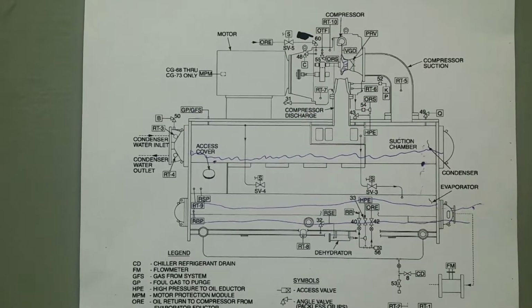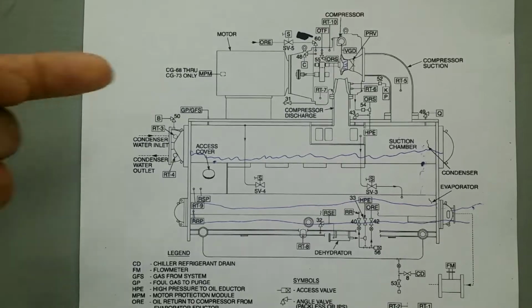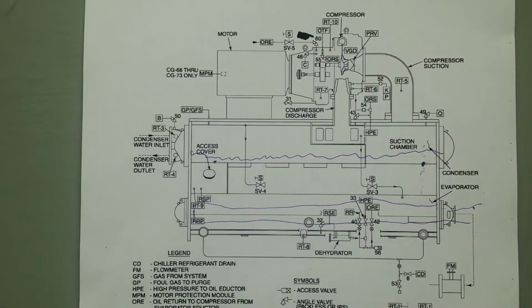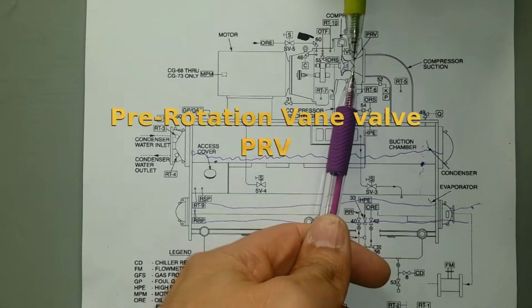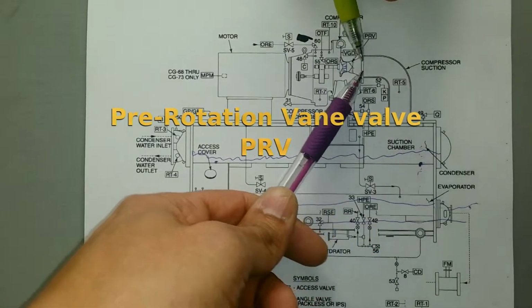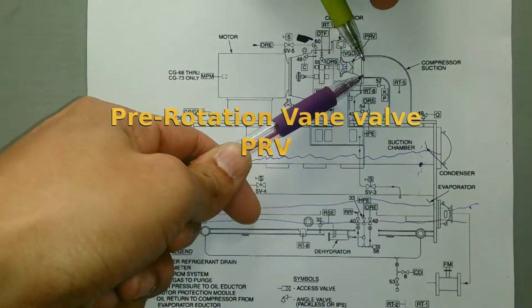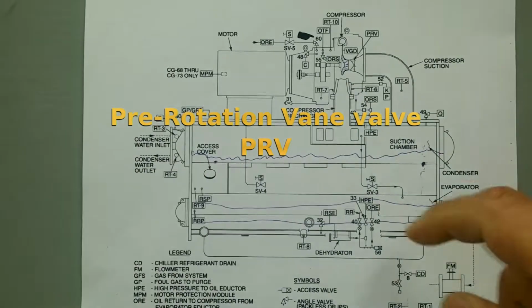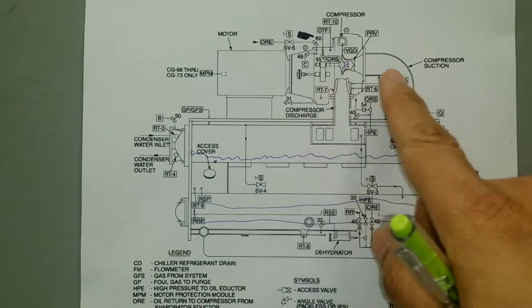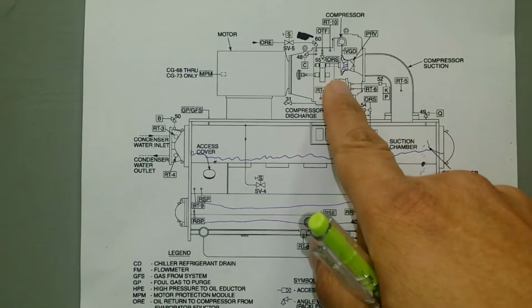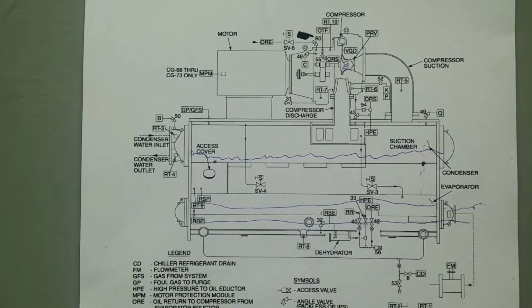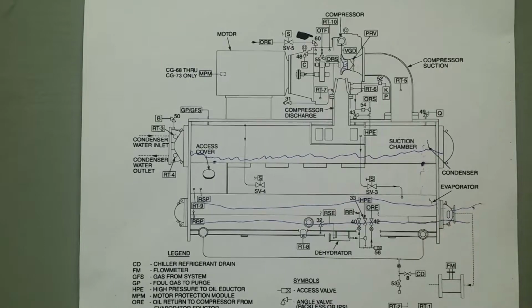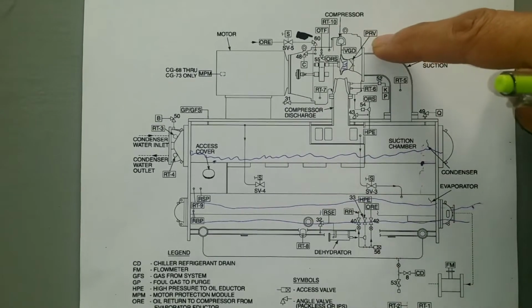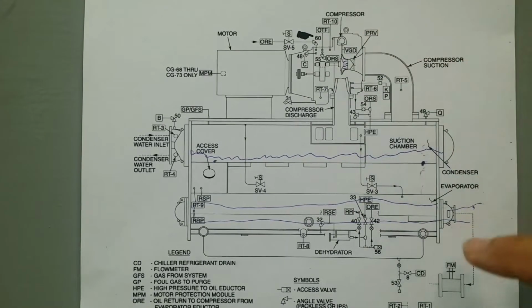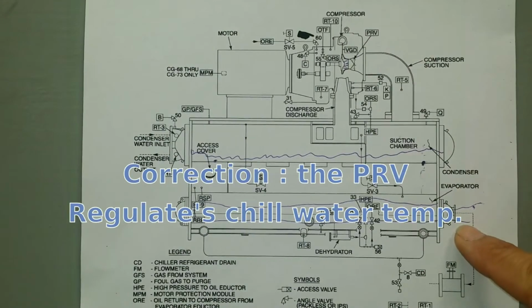We don't want that. To regulate that, and once again, it's because my motor cannot change speeds, there are these pre-rotational vane valves that can open and close. As they close more, they will restrict how much refrigerant gas can go into the compressor. And by doing that, we can regulate the chill water output. So the pre-rotational vane valve regulates chill water.